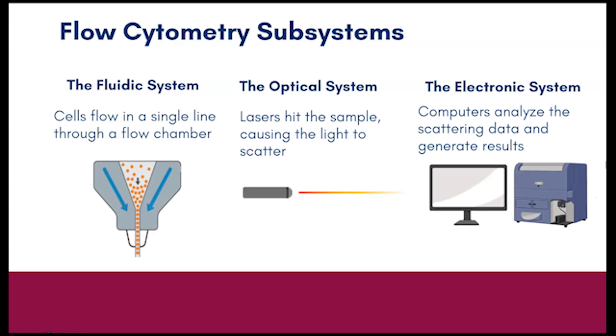Firstly, there's a fluidic system that allows for the flow of cells in a single file line through a flow chamber. Secondly, there's an optical detection system. Lasers are used to strike the sample at what is known as the interrogation point, which causes scattering of the laser light. Various mirrors and filters direct and guide the light towards detectors. Signals are then amplified and converted towards the final component, which involves the computer systems analyzing the data and generating the output results.